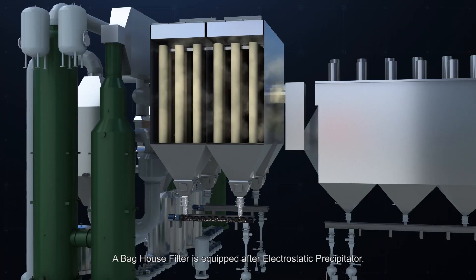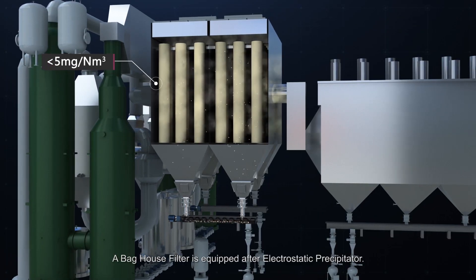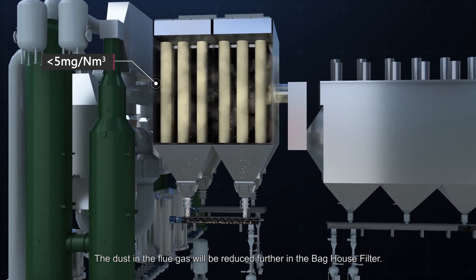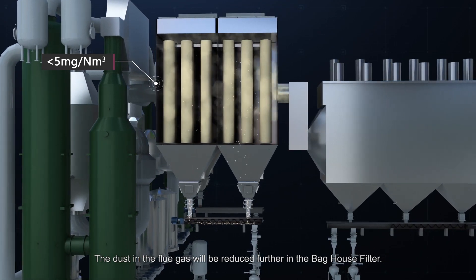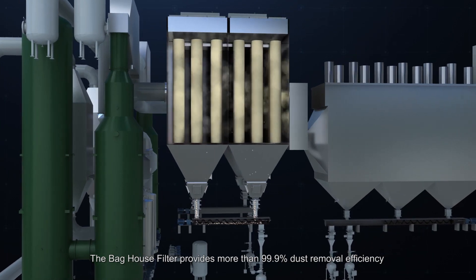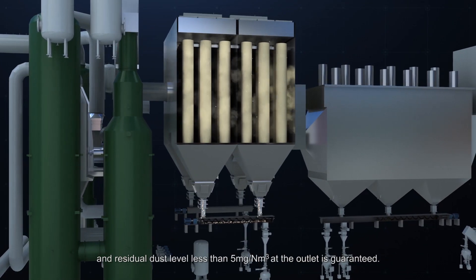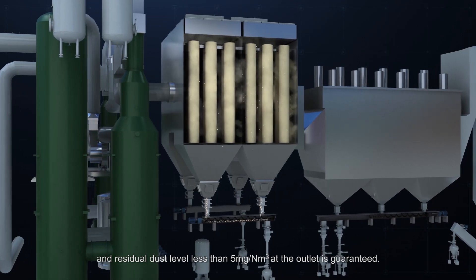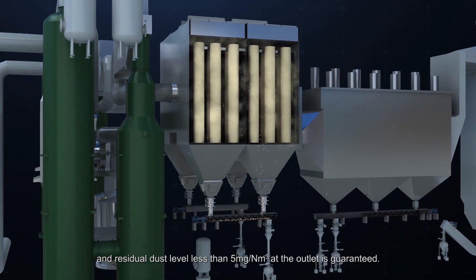A bag-house filter is equipped after electrostatic precipitator. The dust in the flue gas will be reduced further in the bag-house filter. The bag-house filter provides more than 99.9% dust removal efficiency and residual dust level less than 5 mg per normal cubic meter at the outlet is guaranteed.